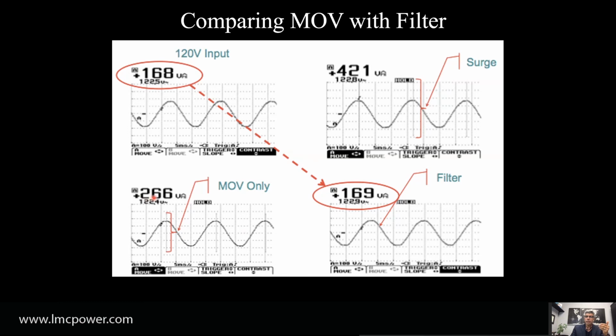But since it has a noise filter as well, we've been able to attenuate the 266 to 169. So in essence, the normal voltage is 168, but because we have transient and filter protection, the equipment will only see an increase of 1 volt at the input of the power supply. So it continues working even under transient conditions and electrical noise conditions.